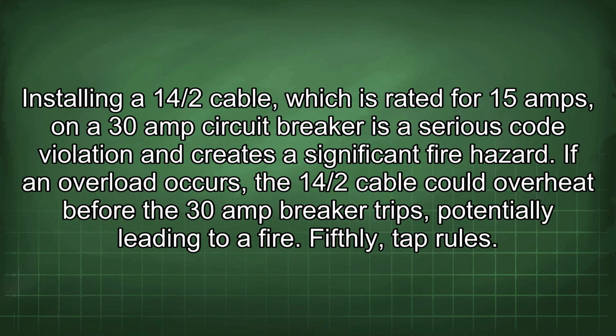Installing a 14/2 cable, which is rated for 15 amps, on a 30 amp circuit breaker is a serious code violation and creates a significant fire hazard. If an overload occurs, the 14/2 cable could overheat before the 30 amp breaker trips, potentially leading to a fire.